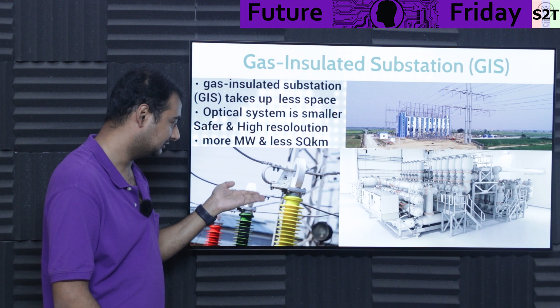Yes, we have what we call these puppies, which can be integrated with the rest of the system. This is what we call optical systems. Utilizing optical fiber, we can sense magnetic fields with surprisingly high accuracy, so you can sense voltage and amps without surface area cost. You could literally put it on both sides of the transformer if you wanted to.